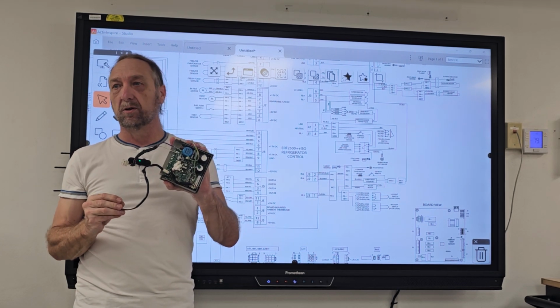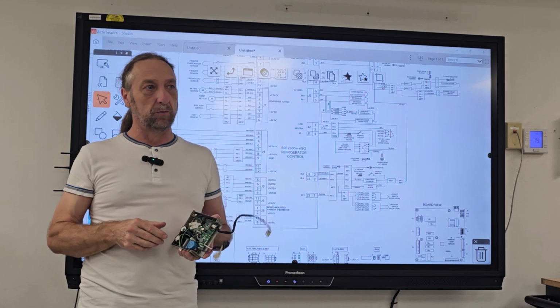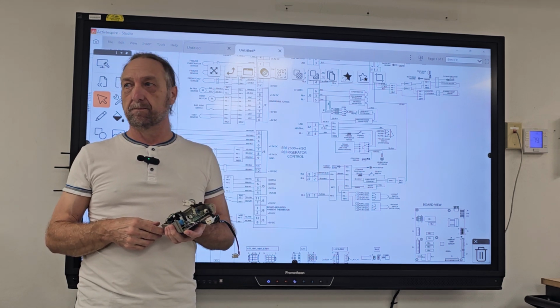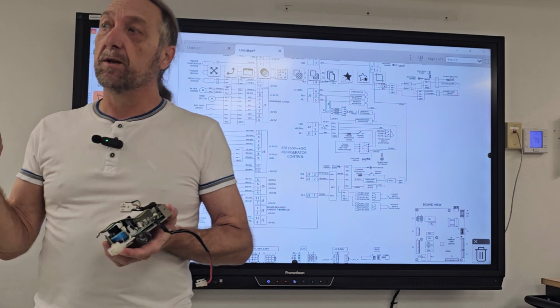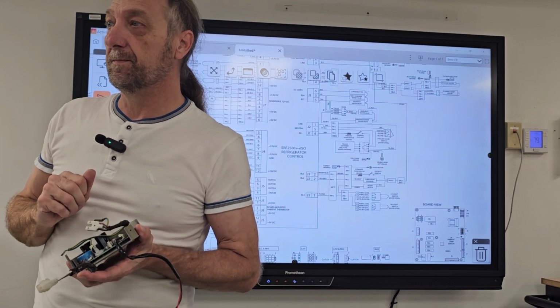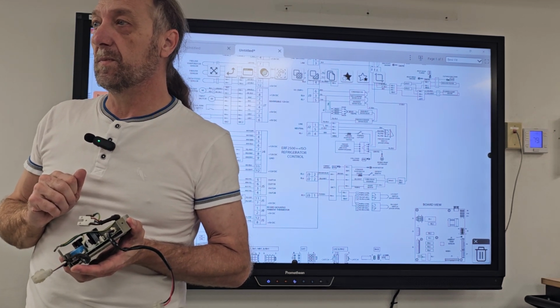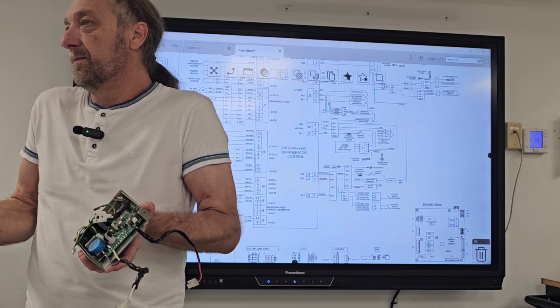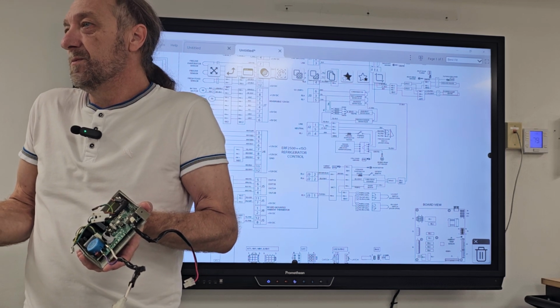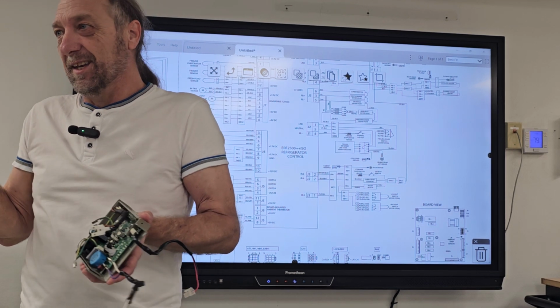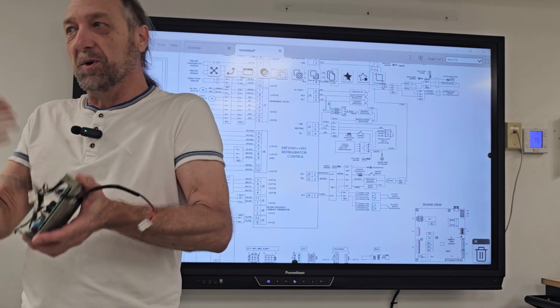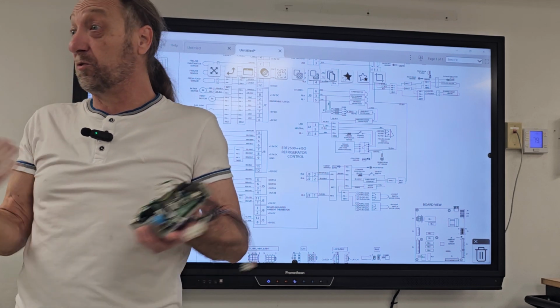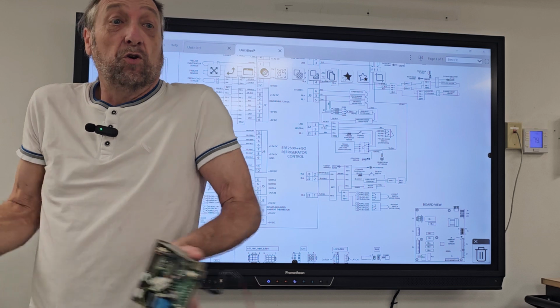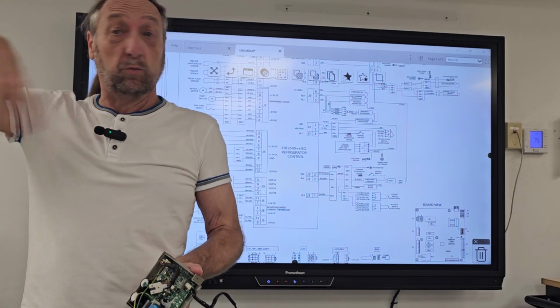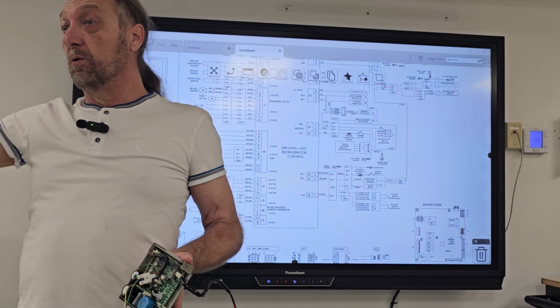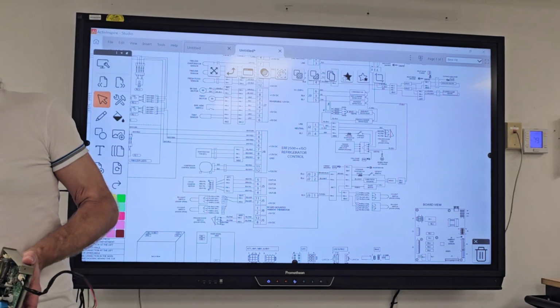If I go to a customer's house and the compressor's not working, I have 120 here and I have 12 volts here, but my compressor doesn't work. What do I do? Check the pressure? But the compressor's not running. Well, sometimes they don't have a pressure switch. It's not like the AC or the ice machine where they have low pressure or high pressure cutouts. Refrigerators don't have that. So if there's no freon in a fridge, the compressor will still run. So checking pressure is the last thing we want to do.